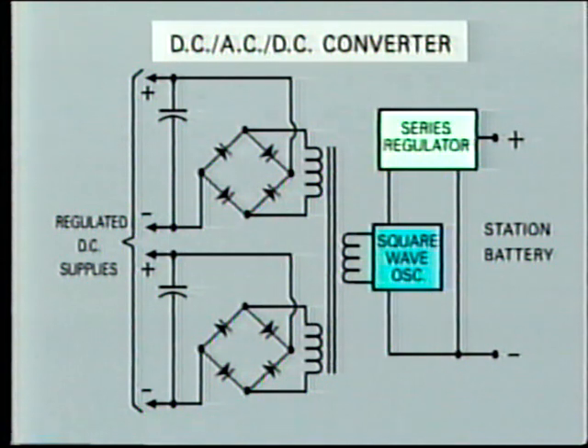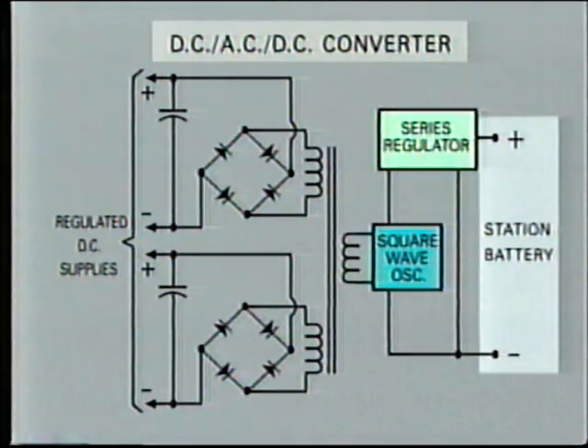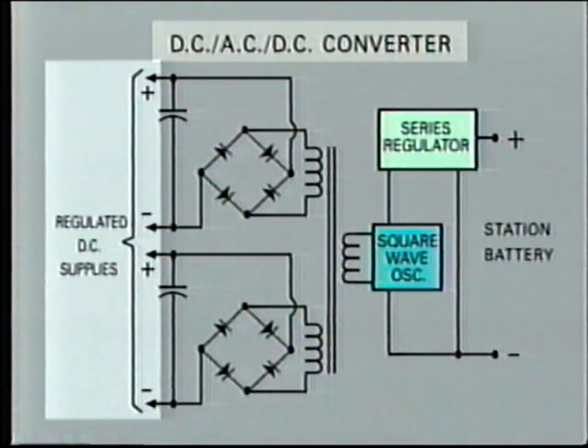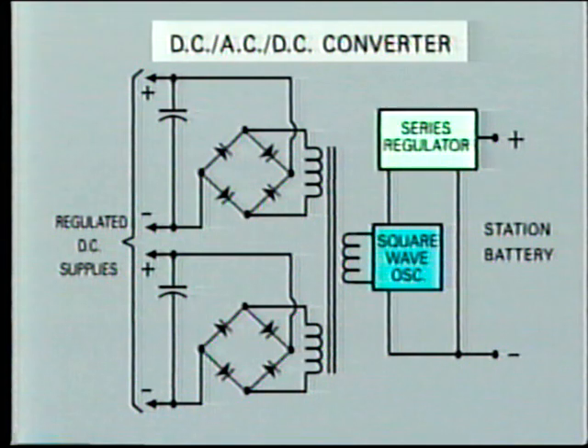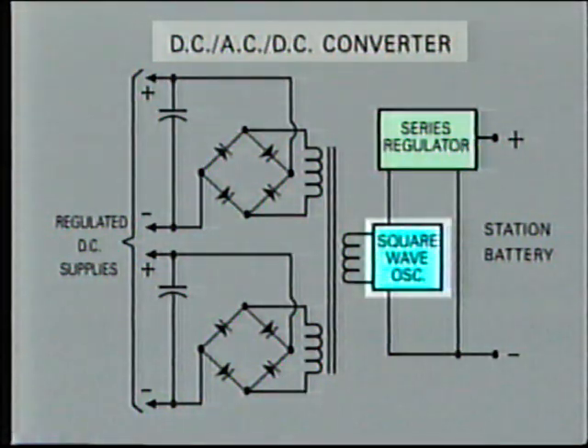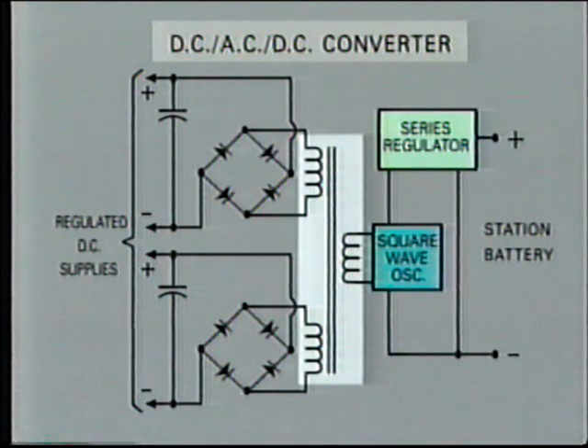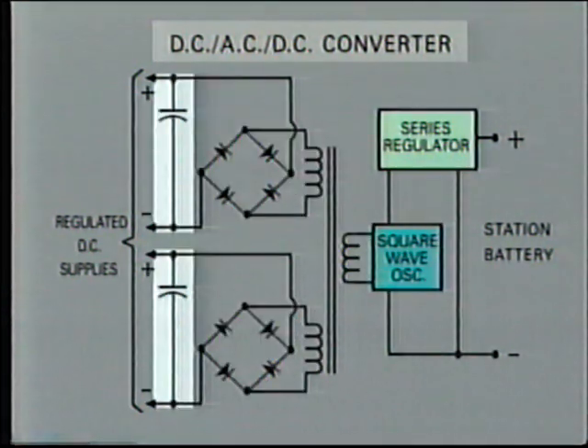In some complex protection schemes, it is preferable to maintain isolation between the DC bus and the relay DC circuit. In this case, a DC/AC/DC converter is installed. The incoming DC is converted to a square wave AC by the oscillator, then transformed, rectified, and filtered.